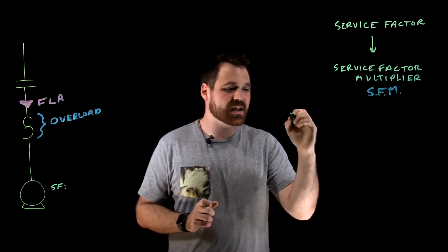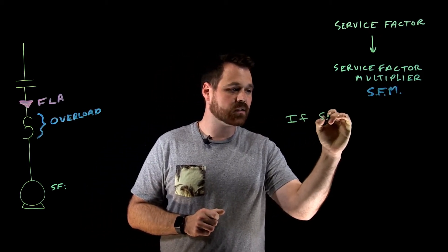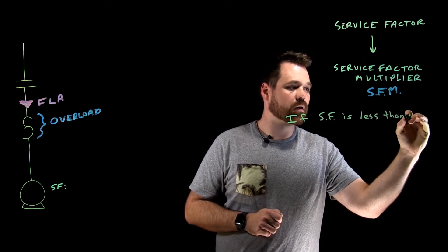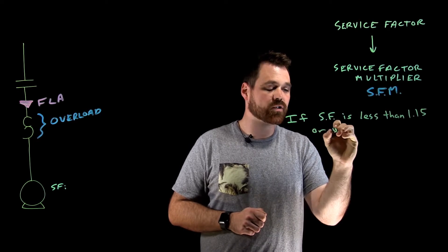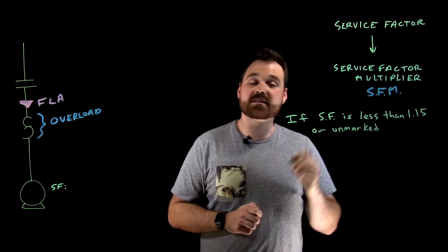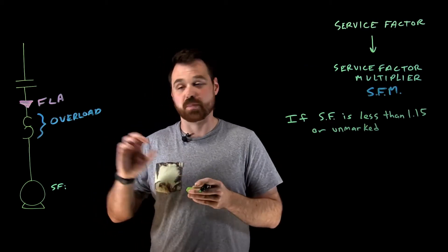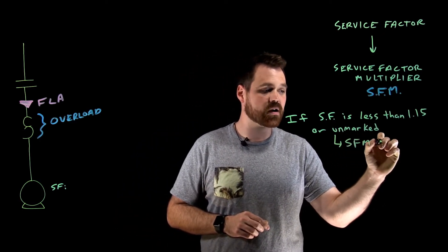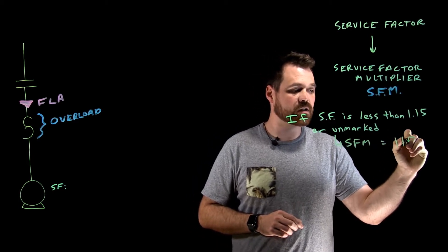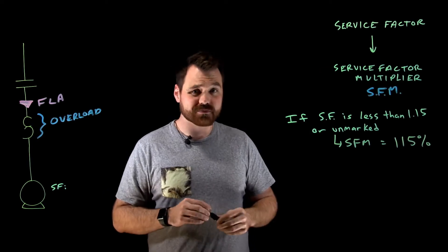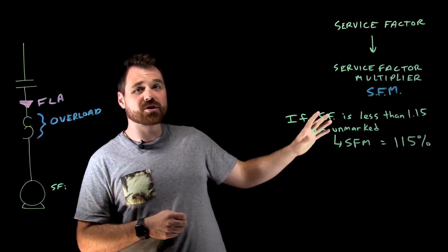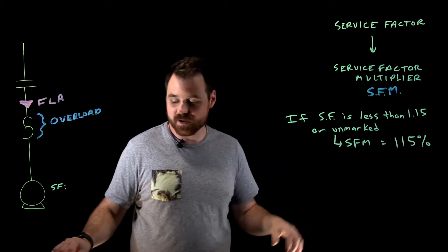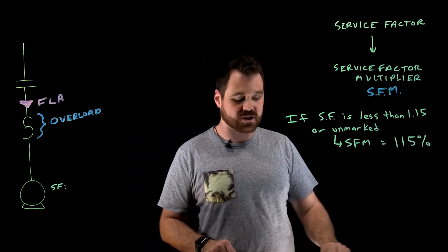The code book tells us if your service factor is less than 1.15 or if your service factor is unmarked, meaning they didn't build the motor good enough to bother putting a service factor on it, so they just left it unmarked, then your service factor multiplier is 115% or 1.15. What that would mean is any motor that has an unmarked service factor, you would assume the service factor is one or if it's less than 1.15.